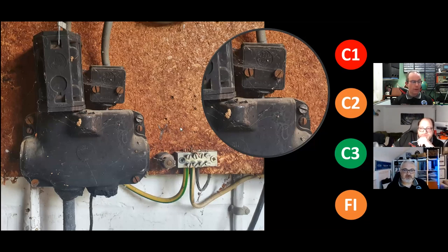Yeah. But what would you code that? Well, the regulations in my head immediately go, oh, there's no safety electrical connection, do not remove label on the external MET. Mm-hmm. So there's a C3 there. But then I look at the rest.